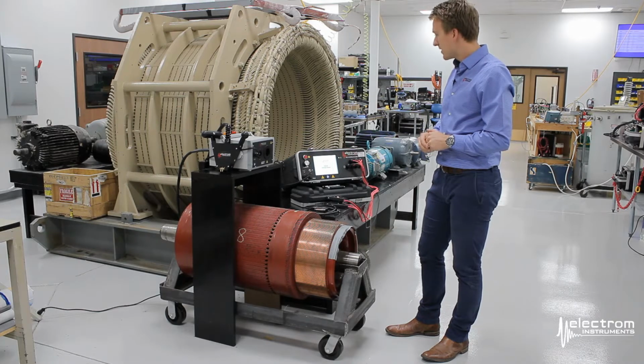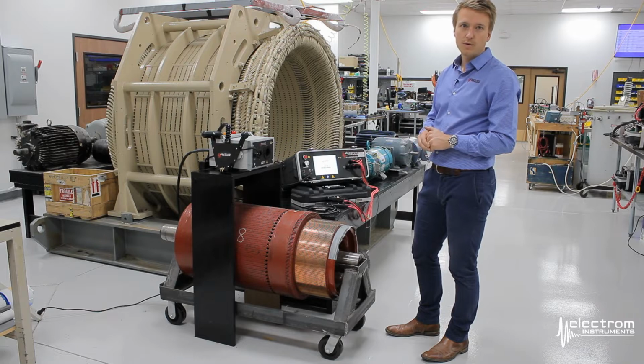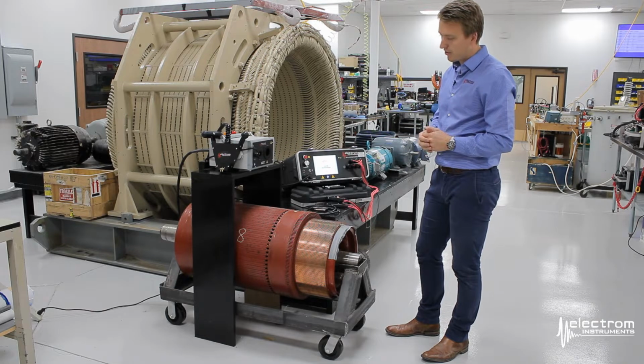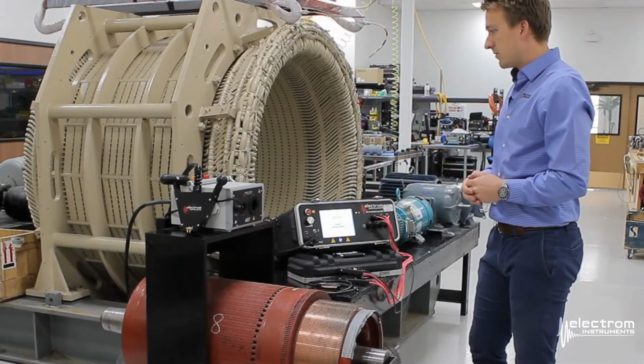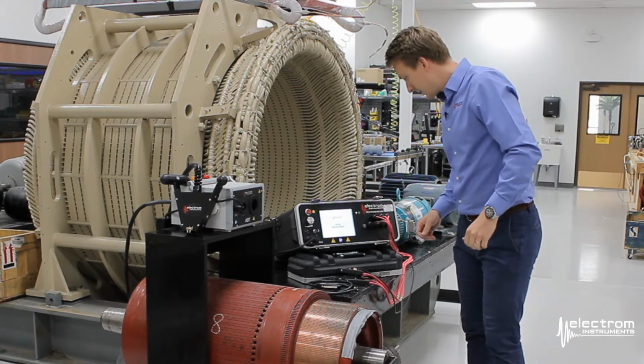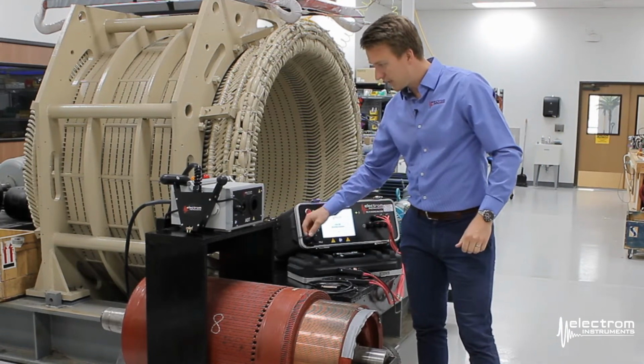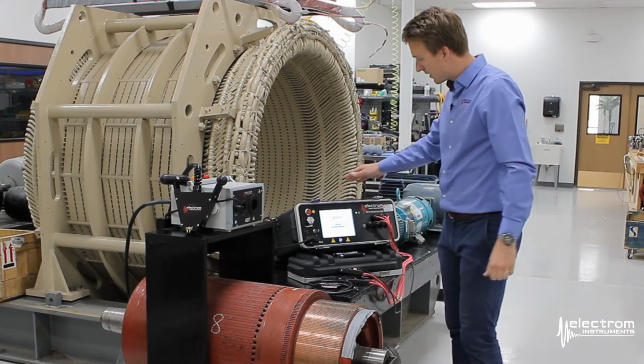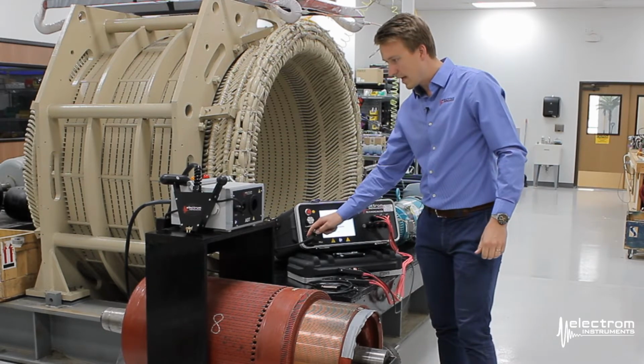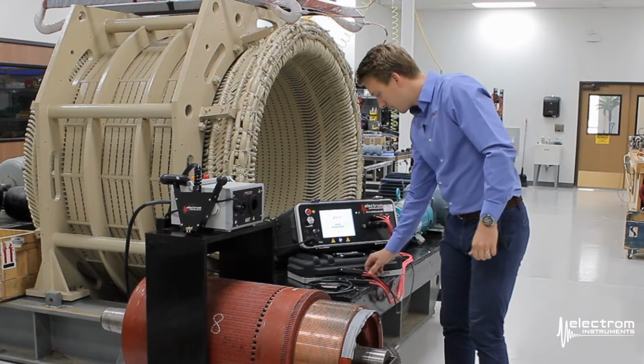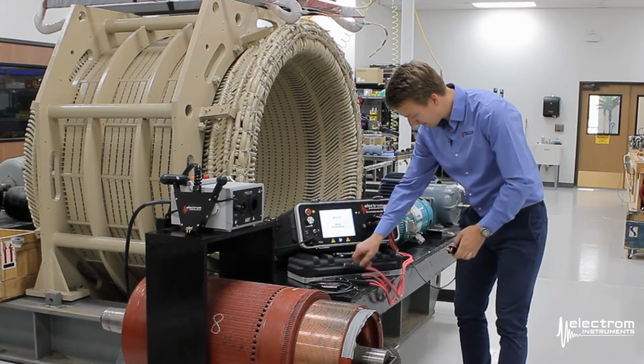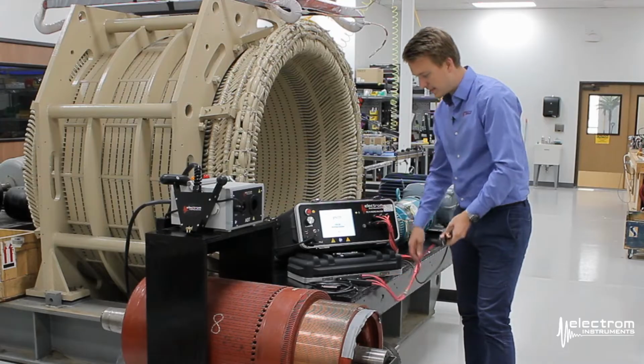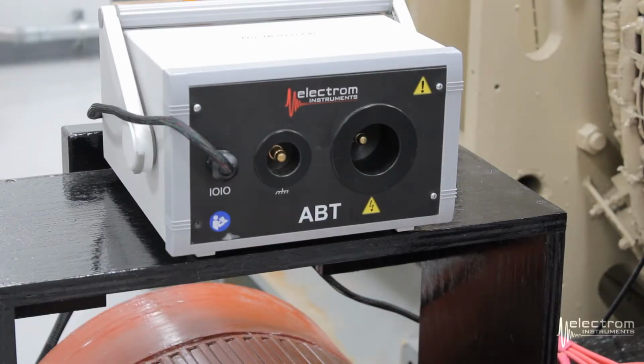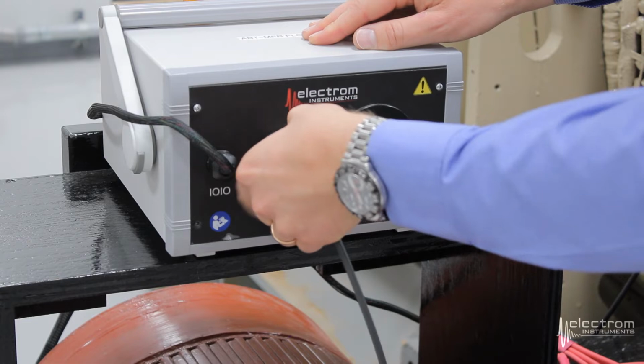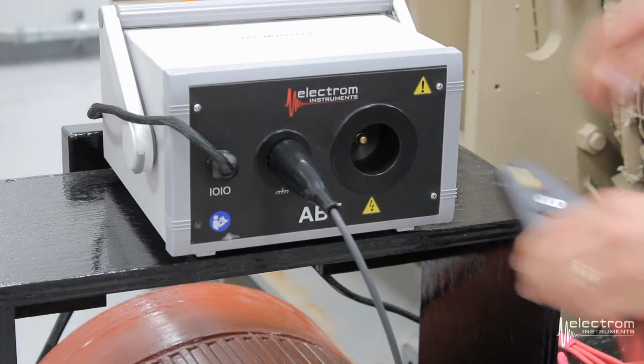The reason why you need a 6 kV or higher is because you want to reach the desired test voltage bar to bar on the armature. To get started, we will connect the low voltage communication cable from the ABT to the instrument. It goes into the A port. Then we will use the ground lead and lead number 1 from the iTIG. The ground clip goes in the ground labeled connector. Lead 1 from the instrument goes to high voltage on the ABT.